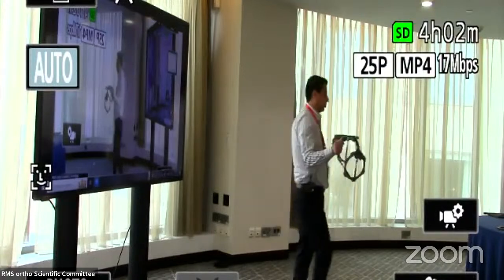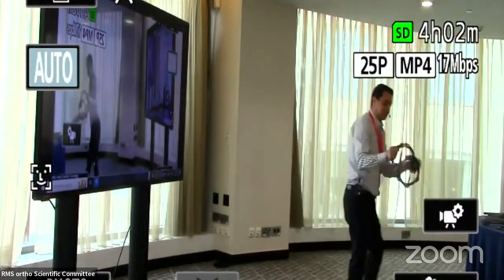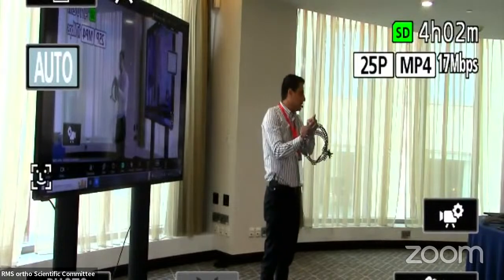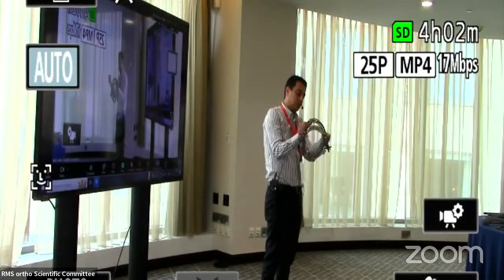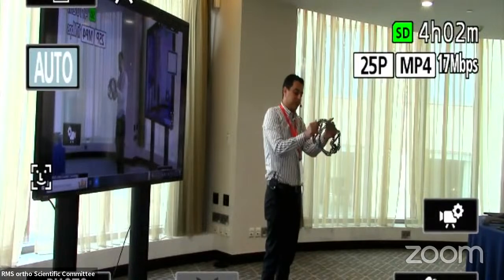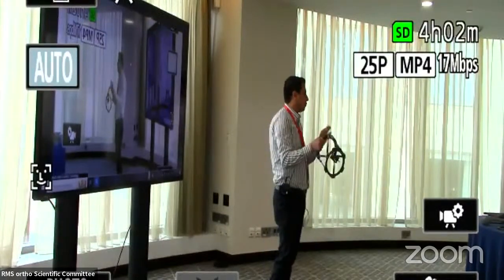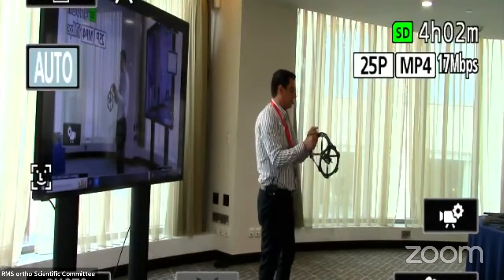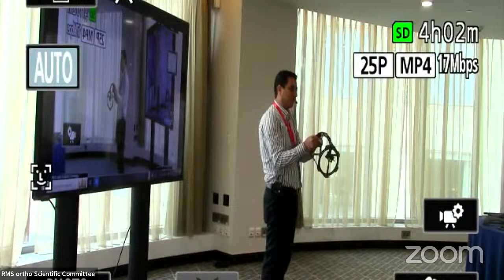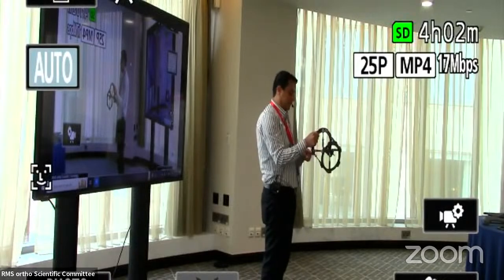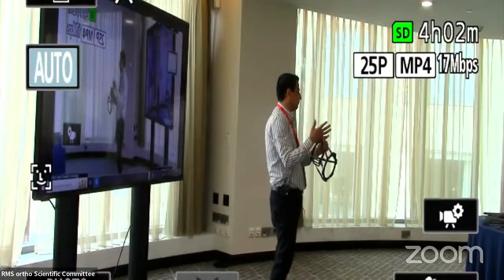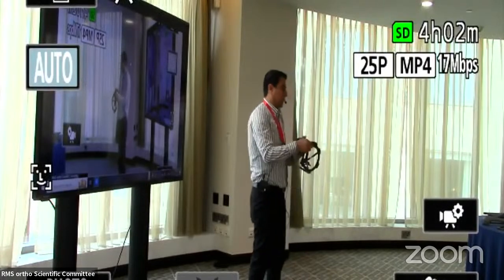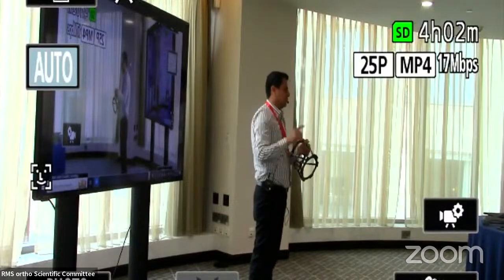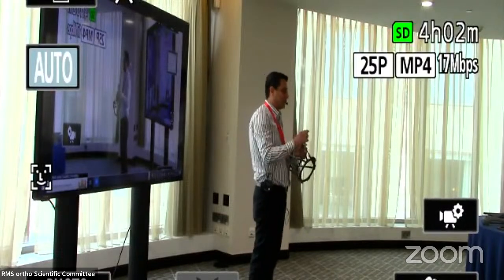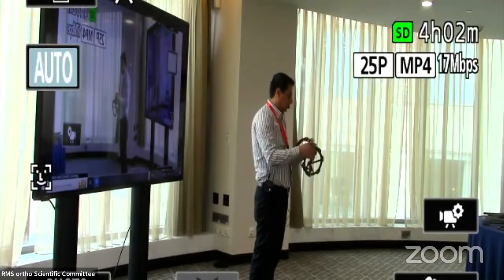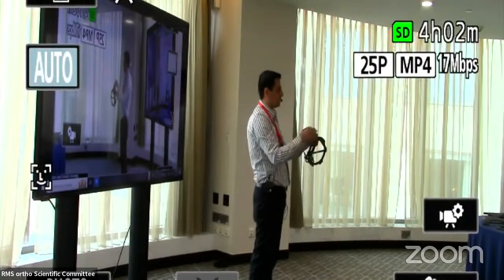How we count or arrange the struts: always start with the master tab, then this is strut number 1, then 2, 3, 4, 5, and 6. And they are color coded, which means the first one is red, then it changes to, I think, orange, then yellow, and by the 6 it is violet. It is the rainbow colors. You have to mark them for the patient, because we will see in a minute how we make the adjustments to do the correction. So it is 2 rings, 6 struts.